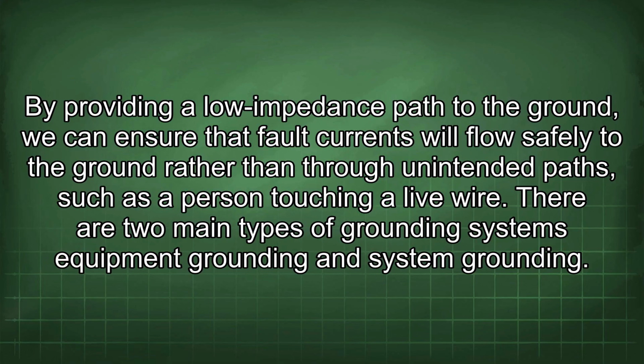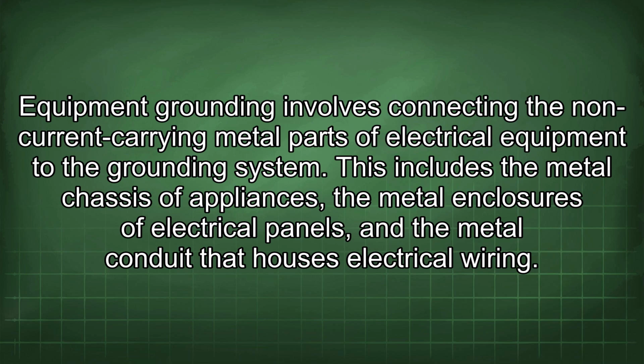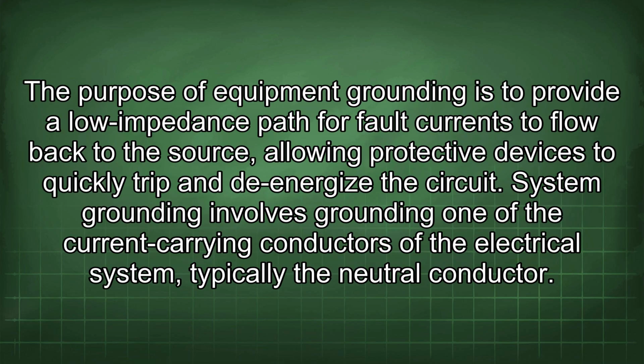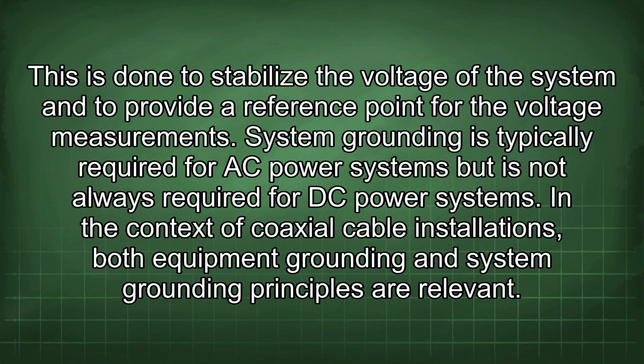There are two main types of grounding systems: equipment grounding and system grounding. Equipment grounding involves connecting the non-current carrying metal parts of electrical equipment to the grounding system. This includes the metal chassis of appliances, the metal enclosures of electrical panels, and the metal conduit that houses electrical wiring. The purpose of equipment grounding is to provide a low impedance path for fault currents to flow back to the source, allowing protective devices to quickly trip and de-energize the circuit. System grounding involves grounding one of the current carrying conductors of the electrical system, typically the neutral conductor. This is done to stabilize the voltage of the system and to provide a reference point for the voltage measurements.